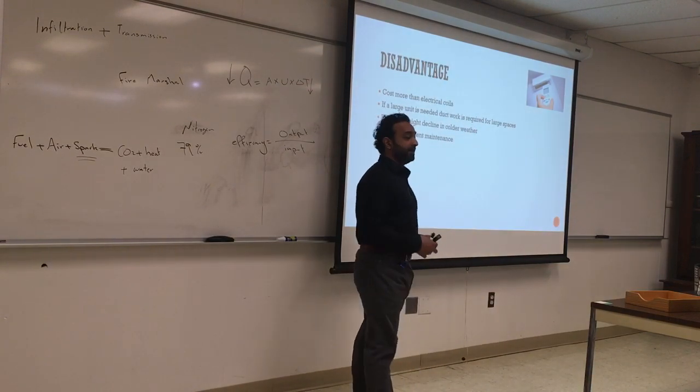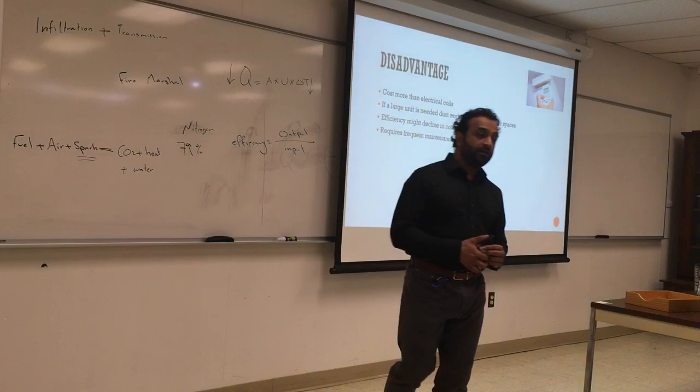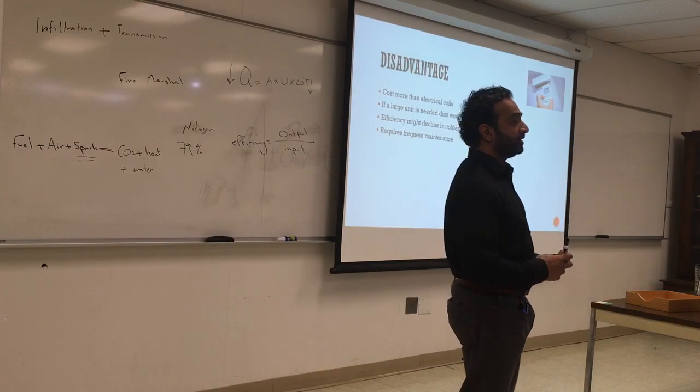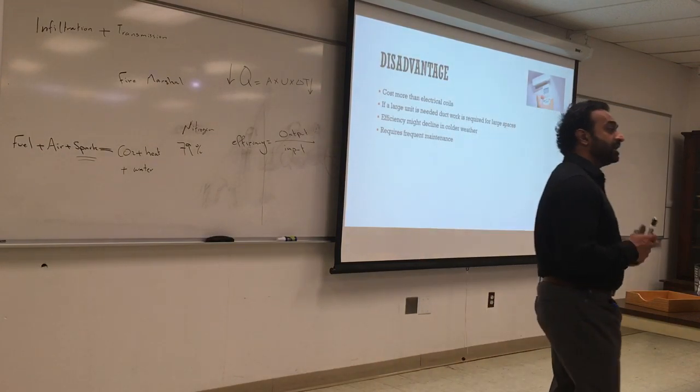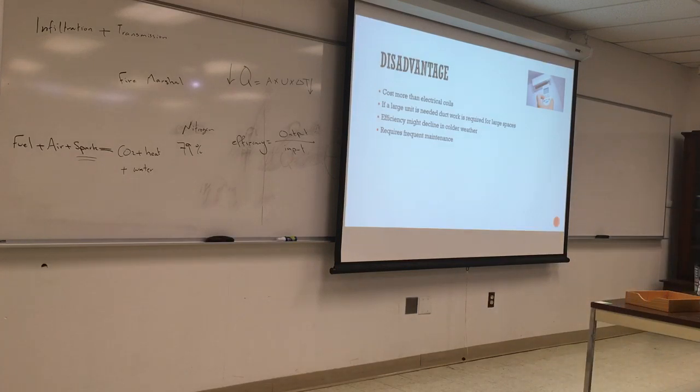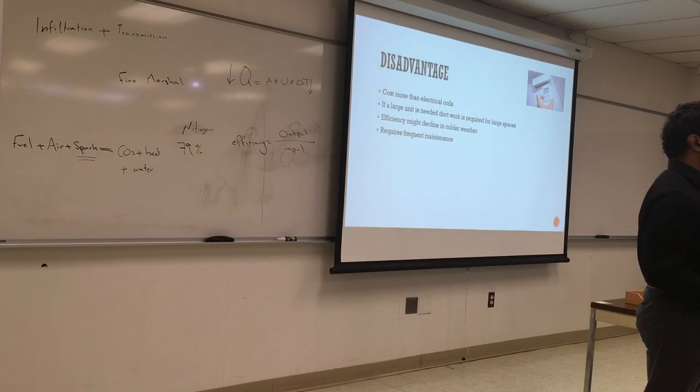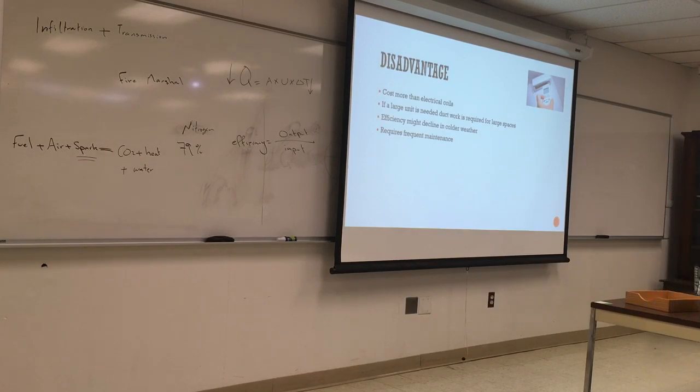Requires frequent maintenance. So what they don't tell you when they sell you this mini split is it requires a lot of maintenance. Somebody has to come every year to measure the amount of refrigerant in the system. It depends on the cost. Most companies give you a 10-year warranty and one annual free maintenance. So it depends on the contract that you have. But it's not something you can skimp on, you have to do the maintenance for these units. They have a warranty for 10 years, but somebody has to come and check the amount of refrigerant and make sure the condenser is clean.